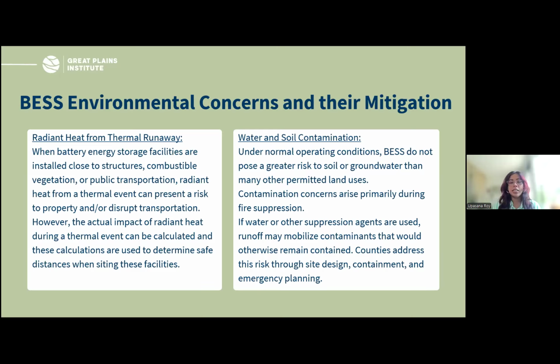The concern that comes from it is the radiant heat when thermal runaway occurs. When these BESS facilities are installed close to structures, have vegetation around, or are within public areas, it can present a risk to the surrounding properties. But again, the codes are very well calculated, and these determine the safety distance for siting these facilities.